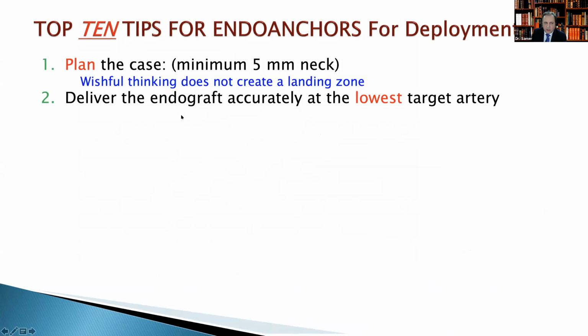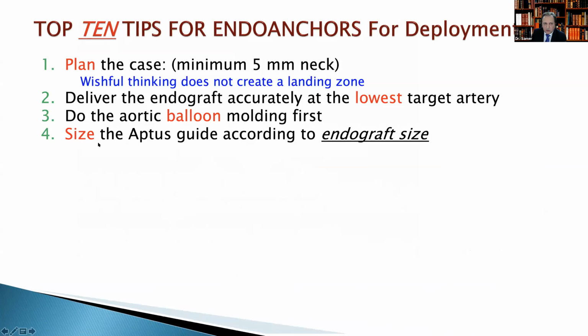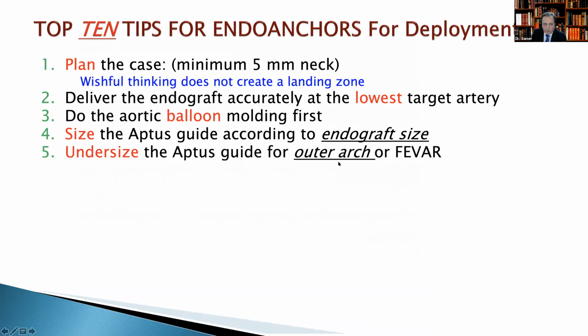The second thing, you need to deploy your device very close to the lowest target vessels. You need to do ballooning first, and then you need to size the Aptus. Usually we size it to the size of the endograft. But if you need to do an Aptus in the outer aorta or in the curve, you need to do an undersize to take the curve.